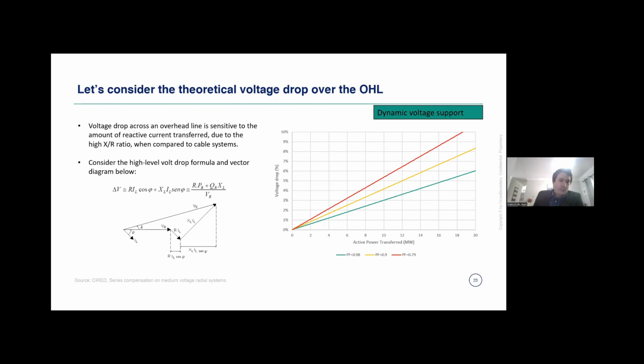So when looking at the theoretical voltage drop across this overhead line, what's important to consider is the impact of power factor, or the impact of the amount of reactive power that you're trying to send across this overhead line. If we look at the graphic that I'm showing here, the green line represents the operation at about 0.98 power factor. And as we move up, the power factor gets worse, and the voltage drop across the line also increases to about 10% at 18 megawatt for a power factor of 0.79, which was the typical power factor of the mine at the time of installation.